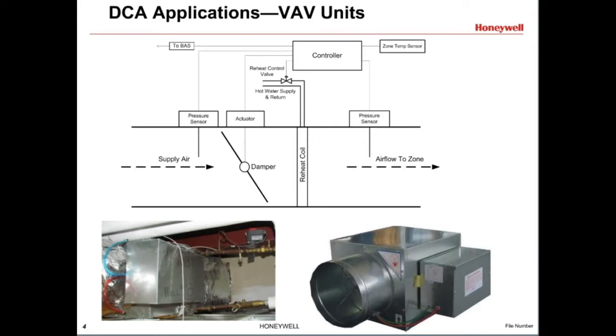VAV, or variable air volume units, also use DCAs. VAVs control the airflow to a specific zone of a building. They are driven to this position one of three ways. They may be floating, where the actuator is driven open or closed and then stopped at a certain position, or they may be proportional, where the control signal of a certain voltage or amperage is used to instruct the actuator to drive to a certain position. And lastly, actuators may communicate with the controller using computerized signals over a communicating bus.